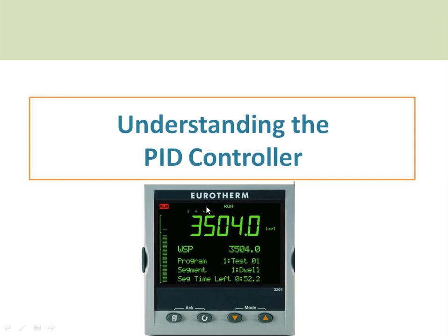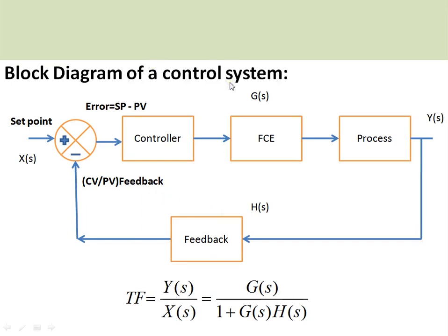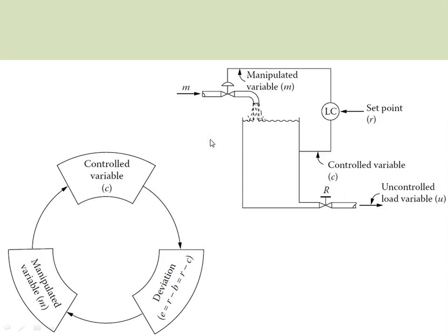This is the block diagram of a typical control system. The controller is the brain of your control system, which sends commands to the final control element. For example, if your process is a furnace where temperature needs to be maintained at a constant value, the temperature is measured by a feedback device like a thermocouple or RTD and fed back to the controller. The controller then commands the final control element — in this case, a thyristor drive — which controls the voltage fed to the heating element of the furnace.